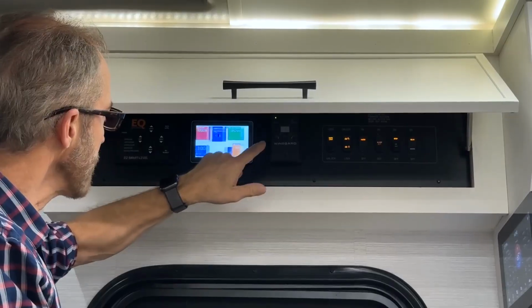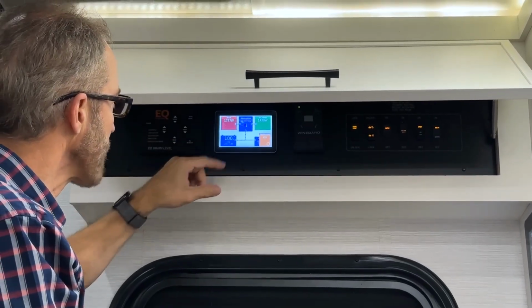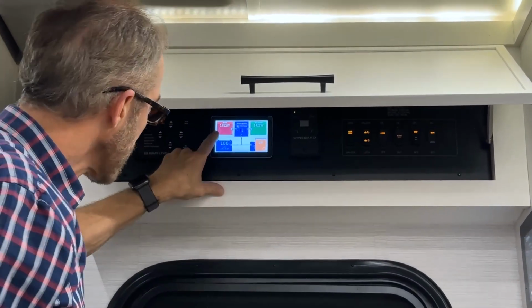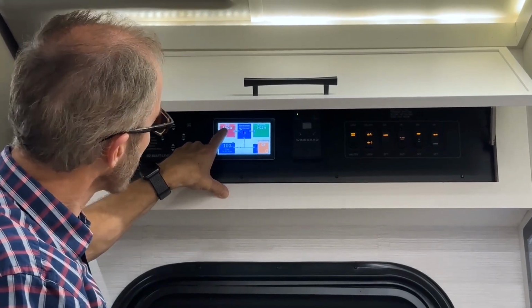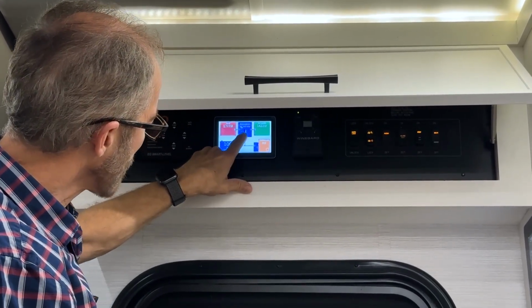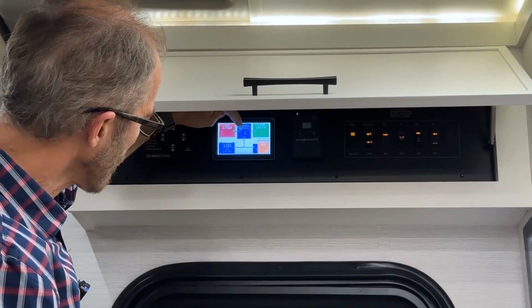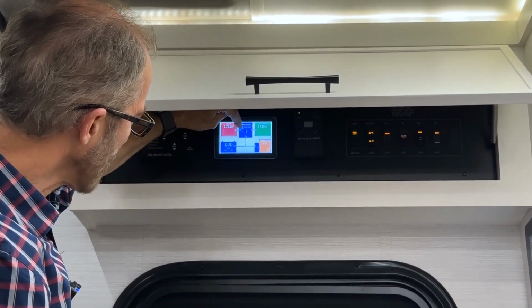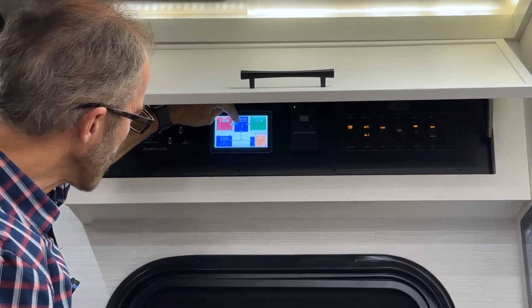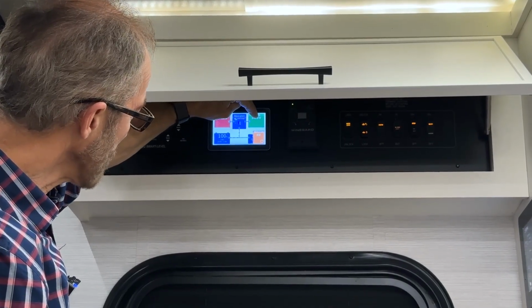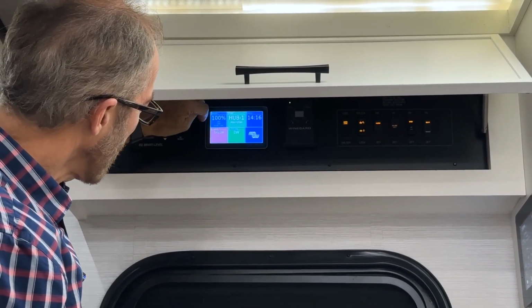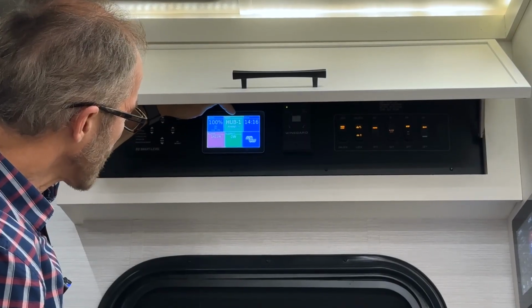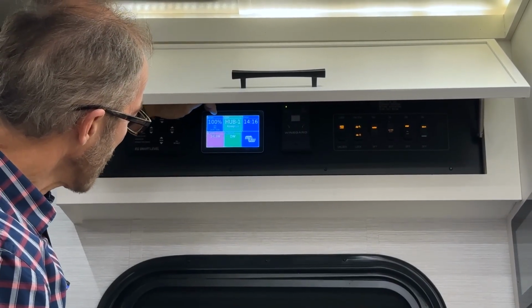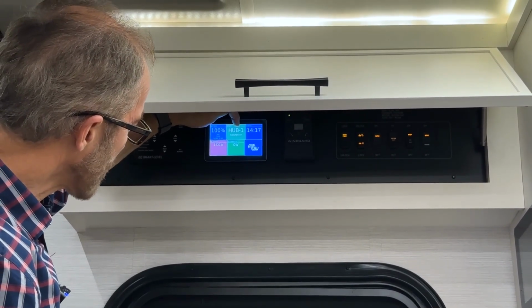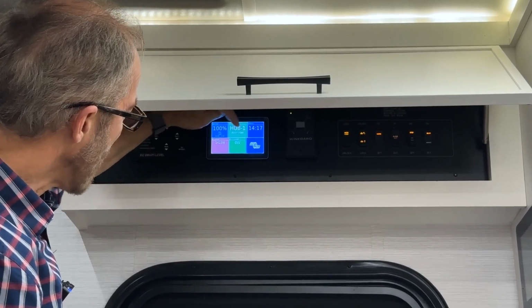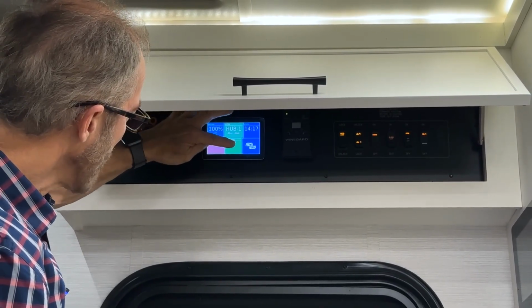On the main screen, you can scroll back and forth through two separate pages. Basically it tells you what your grid power is coming in. It shows your inverter is turned on with the green switch at the top left LED there - that's where it needs to be. It gives you your AC loads. On the second page, it tells you your battery state is 100% charged, it's an absorption charge, and it tells you what your AC loads are.